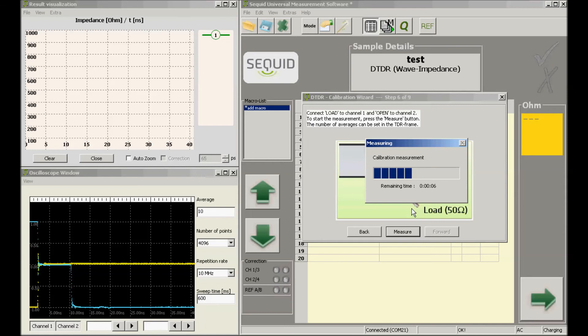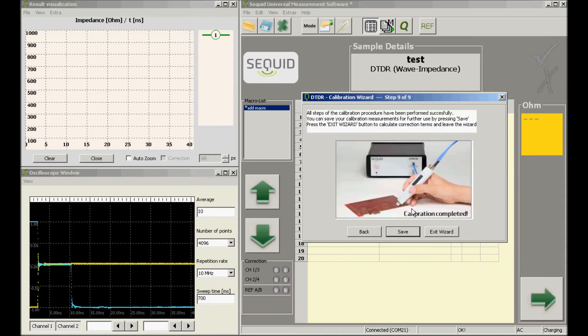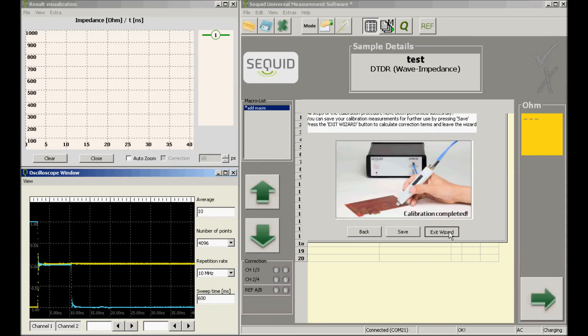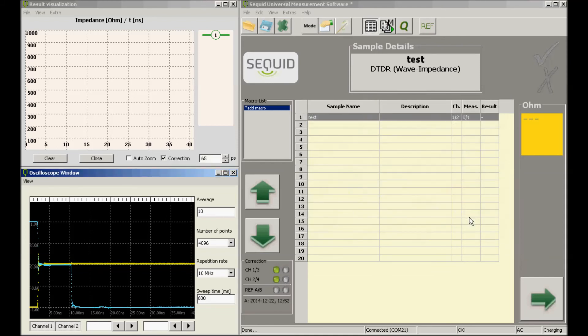After finishing the last measurements, the calibration is done and we come to the last window. It is usually not needed to save the calibration explicitly. We exit the wizard and the three-term calibration is stored automatically at a predefined location. The two green LEDs at the left are turned on, indicating that the three-term correction is now activated.